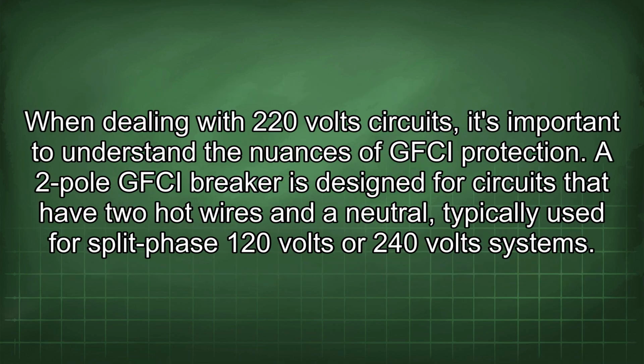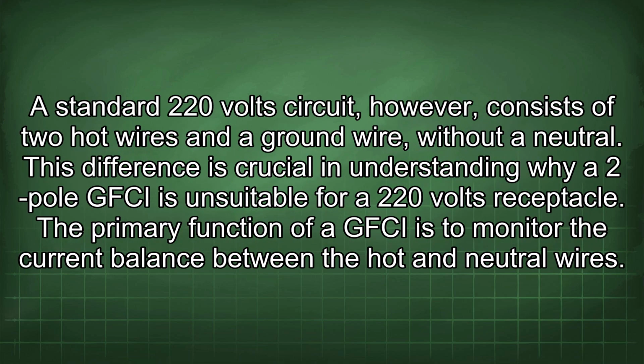When dealing with 220-volt circuits, it's important to understand the nuances of GFCI protection. A two-pole GFCI breaker is designed for circuits that have two hot wires and a neutral, typically used for split-phase 120 volts or 240 volts systems. A standard 220 volts circuit, however, consists of two hot wires and a ground wire, without a neutral. This difference is crucial in understanding why a two-pole GFCI is unsuitable for a 220 volts receptacle. The primary function of a GFCI is to monitor the current balance between the hot and neutral wires.